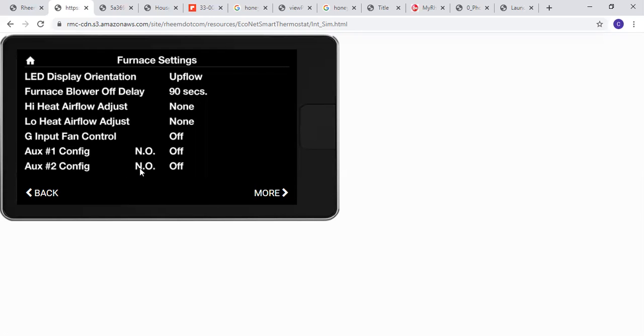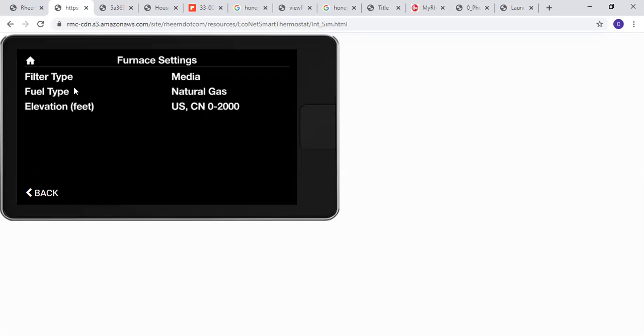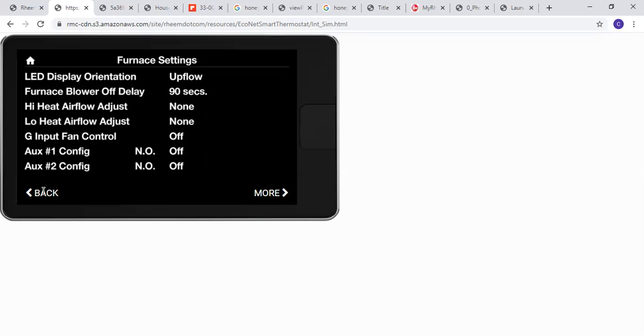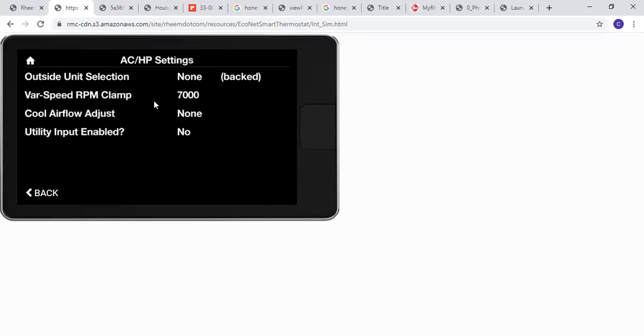If we're using a smoke detector, float switch, whatever you have. And here's where you put in your filter type, fuel, and elevation. In this case here, there is no outdoor unit selection. If it's a communicating system, it'll say EcoNet locked. Or if it's a non-communicating, you can go in here and configure it to be non-communicating, AC, heat pump, what have you.